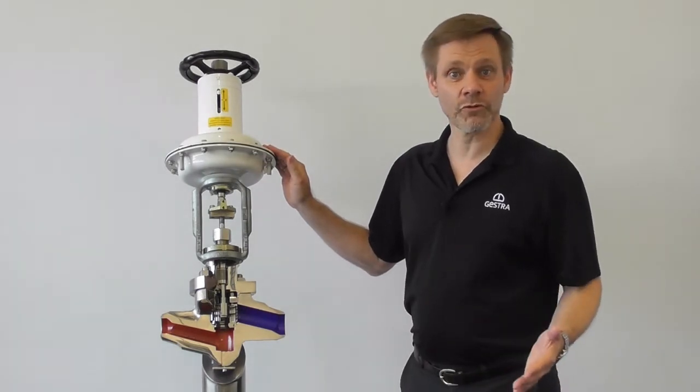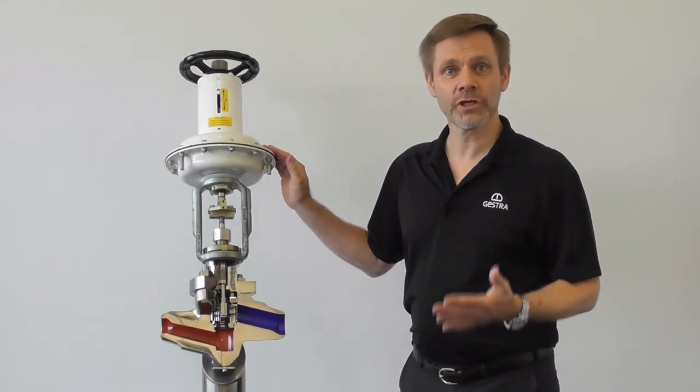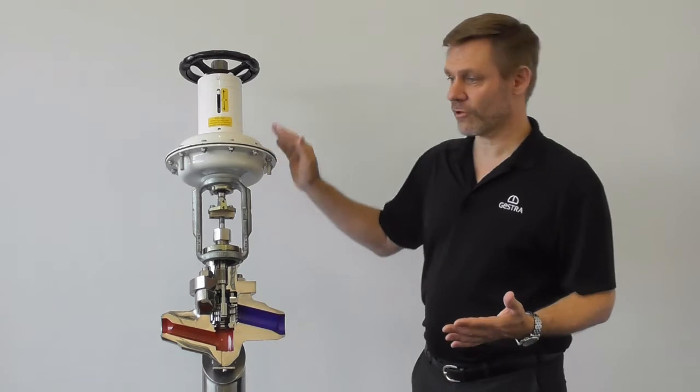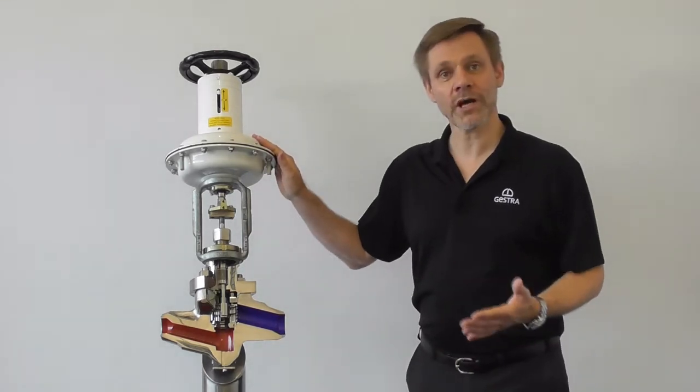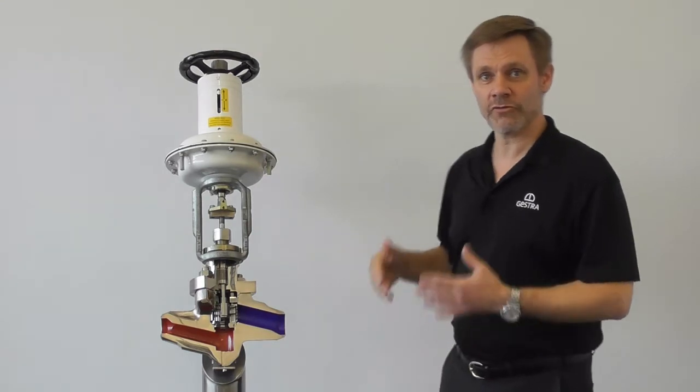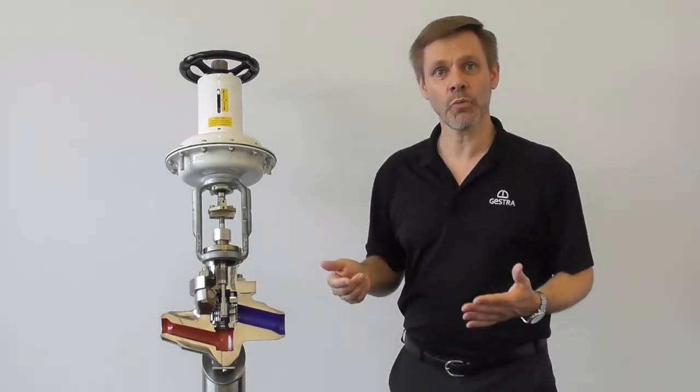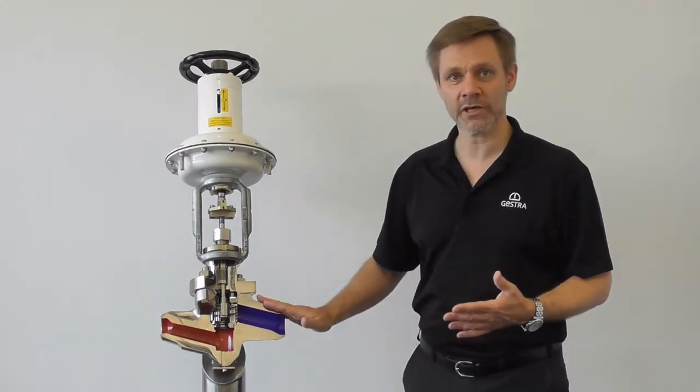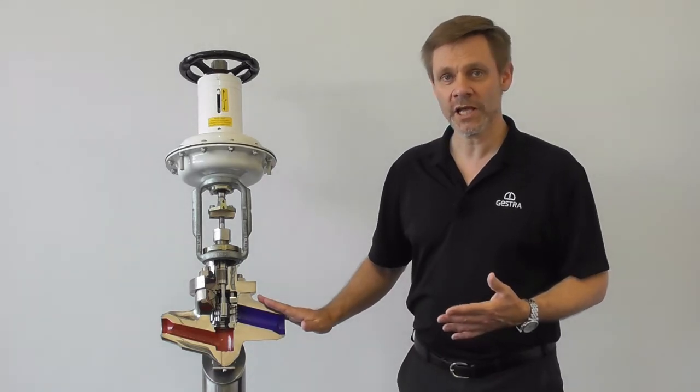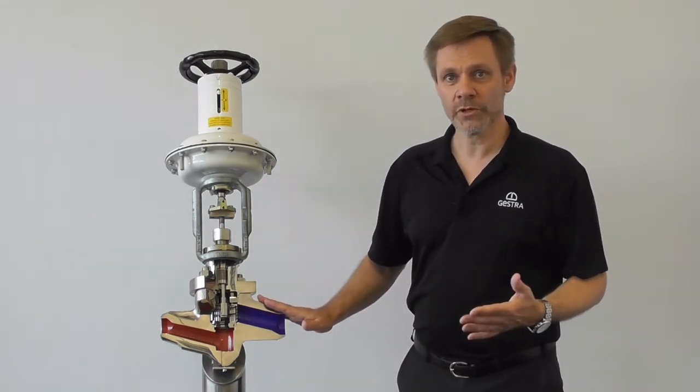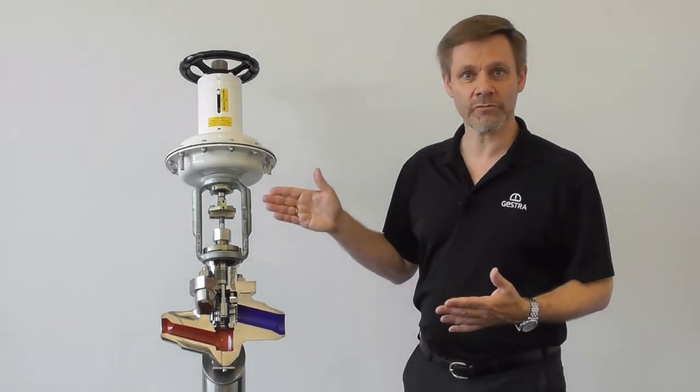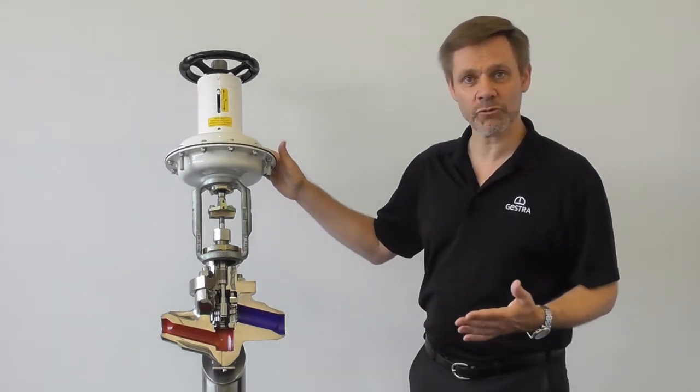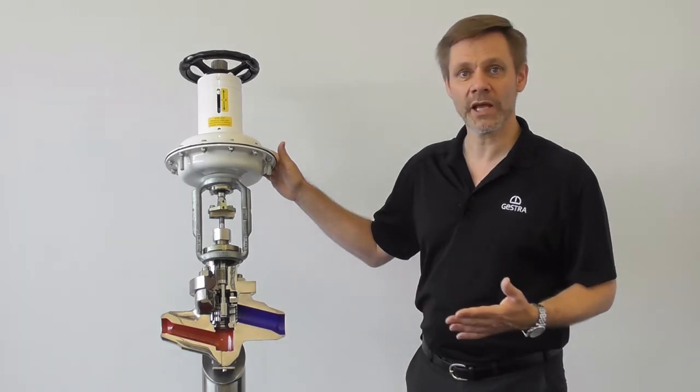The GESTRA control valves are an excellent solution for energy saving, to keep the productivity of your plant and to reduce the maintenance costs. It's a reliable valve in the size from 1 inch up to 6 inch. The trim design is suitable for differential pressures up to 100 bar or 1450 psi. Pressure class is class 900, nominal pressure PN160. And we have the opportunity to equip the valve with different types of actuators. On one hand, here we see a pneumatic diaphragm actuator. Even electric actuators are possible or simple hand wheels.